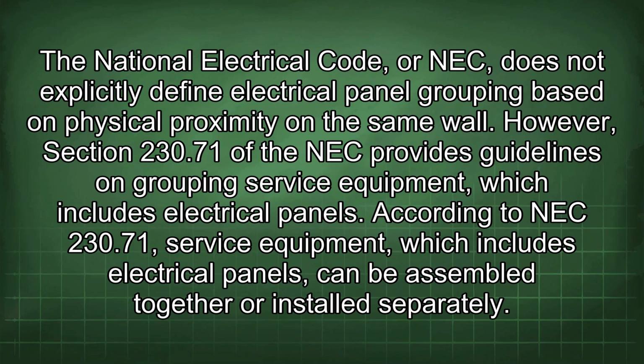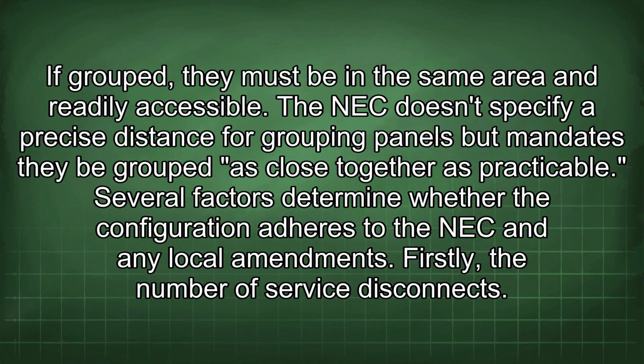The National Electrical Code, or NEC, does not explicitly define electrical panel grouping based on physical proximity on the same wall. However, Section 230.71 of the NEC provides guidelines on grouping service equipment, which includes electrical panels. According to NEC 230.71, service equipment can be assembled together or installed separately. If grouped, they must be in the same area and readily accessible. The NEC doesn't specify a precise distance for grouping panels, but mandates they be grouped as close together as practicable.